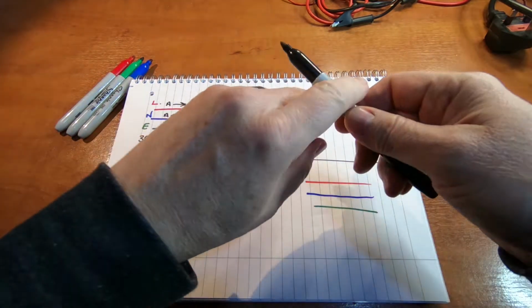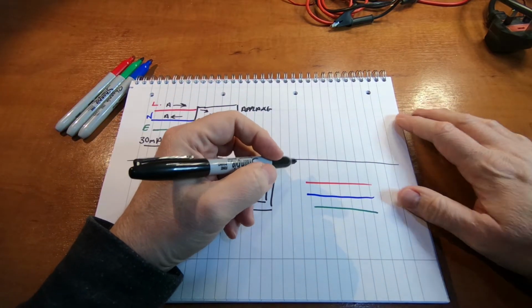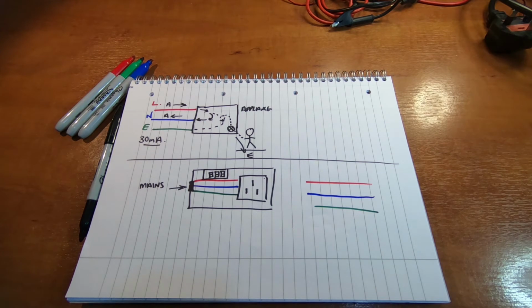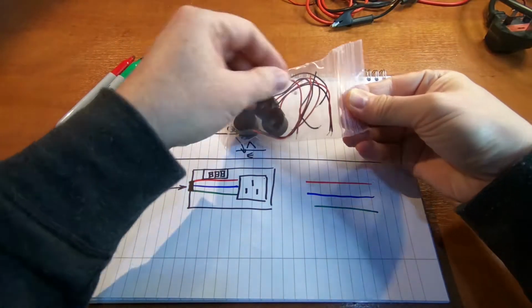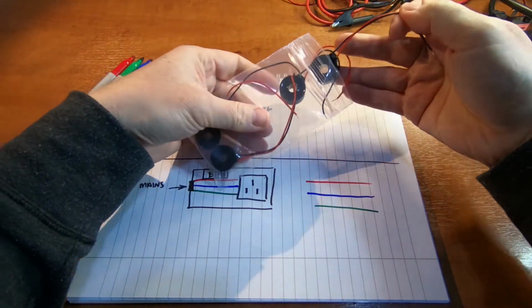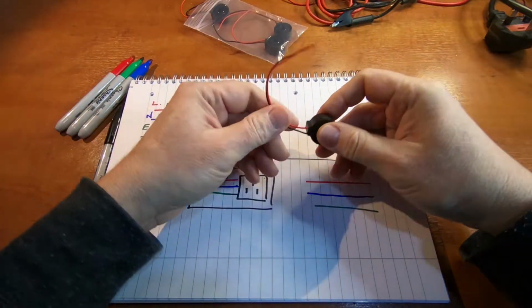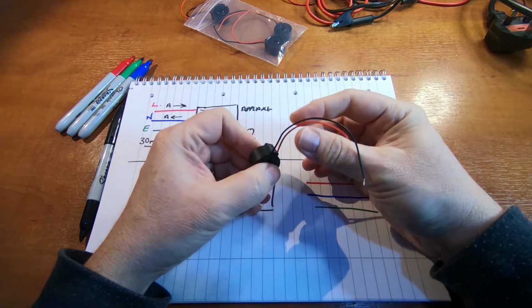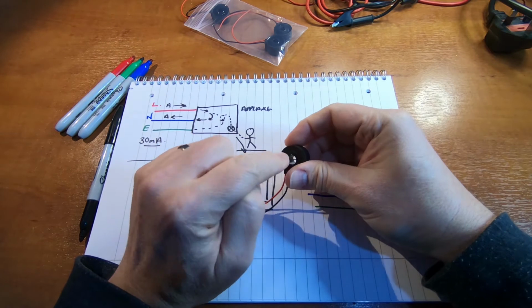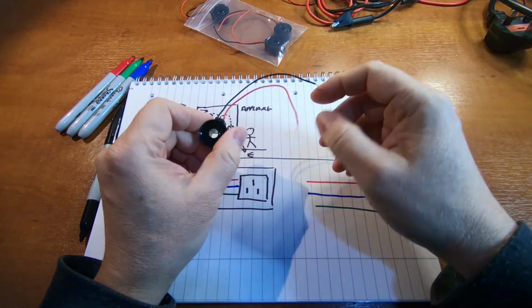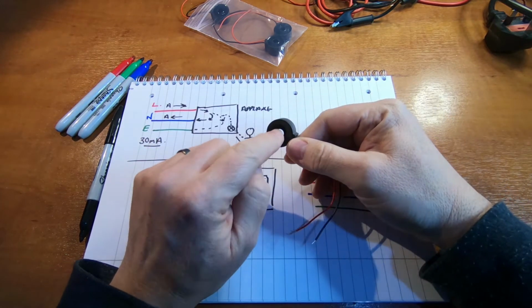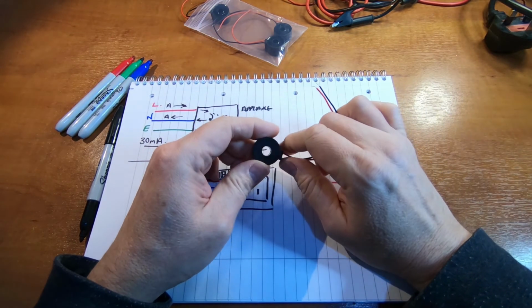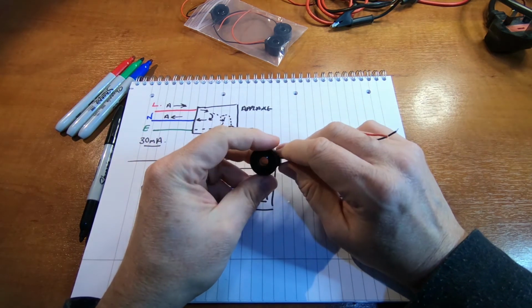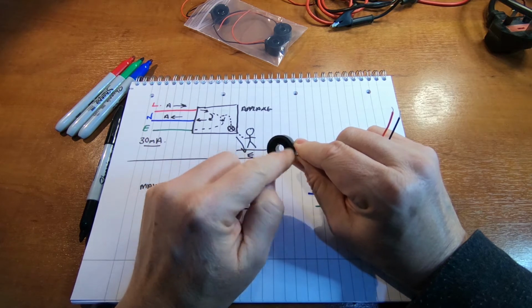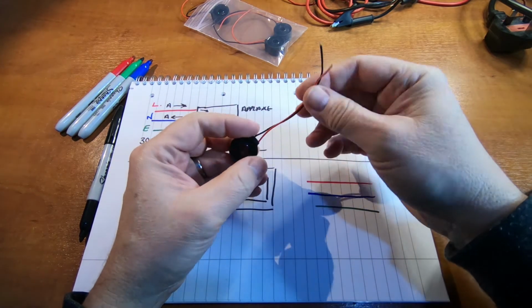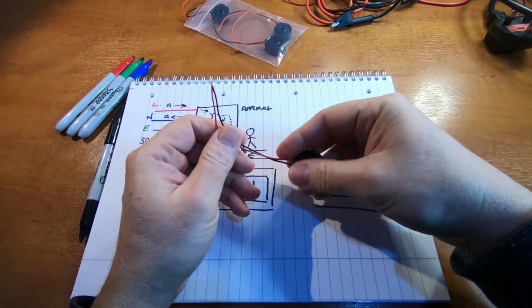So what I'm thinking is to use a current transformer. You may have seen those. I've got some here, just 1 second. So I had these just knocking around. I've never used them, but these are current transformers, and the way these work is you put your conductor through the center of here, and there'll be a voltage generated on these when a current flows through it, because it's a transformer. These are 2000 to 1 turns, so the 1 is the single conductor through the middle, and there's 2000 turns on that transformer. And I haven't tried any of these yet. This is just a thought process at the minute.